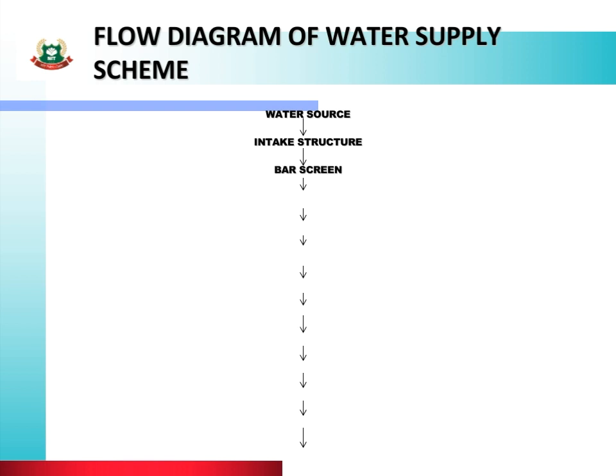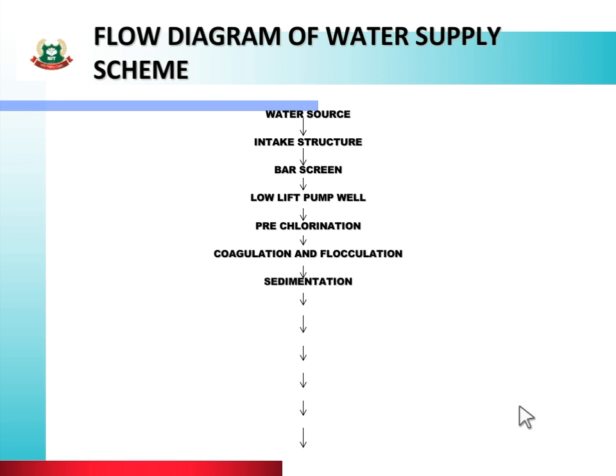Next we will see the flow diagram of the water supply scheme, showing how water is taken from the source to the consumer. Water comes from the water source to the intake structure. From the intake structure, water passes through a bar screen to the low lift pump well. From there, water goes through various treatment processes: pre-chlorination, coagulation and flocculation, sedimentation, filtration, and post-chlorination. Finally, it is collected in a sump well, from where water is pumped to an elevated service reservoir through a high lift pump, and then distributed through the distribution system.